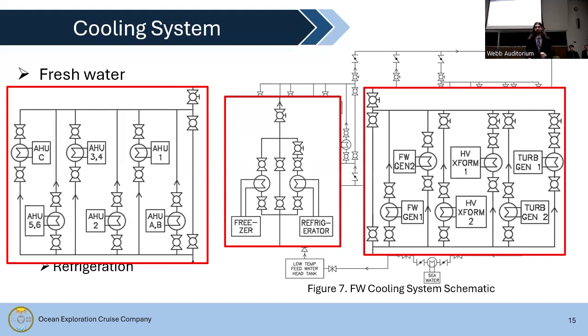From left to right, the secondary loops consist of the HVAC, refrigeration, and auxiliary machinery. Each secondary loop takes cooling water from the supply manifold. The components in each secondary loop are connected in parallel. The outlet water for each loop passes through a throttling valve to equalize the pressure before all the loop outlets flow into a common return manifold.